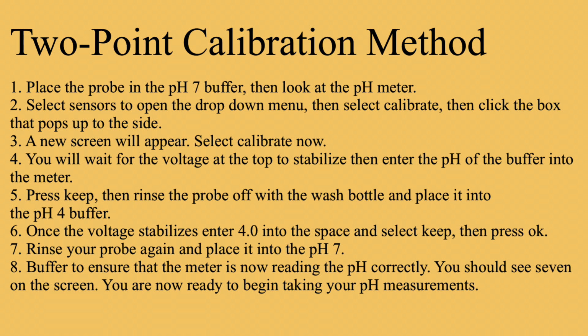Select Calibrate now. You will wait for the voltage at the top to stabilize, then enter the pH of the buffer into the meter. Press Keep, then rinse the probe off with the wash bottle that has distilled water and place it into the pH 4 buffer. Once the voltage stabilizes, enter 4 into the space and select Keep, then press OK.